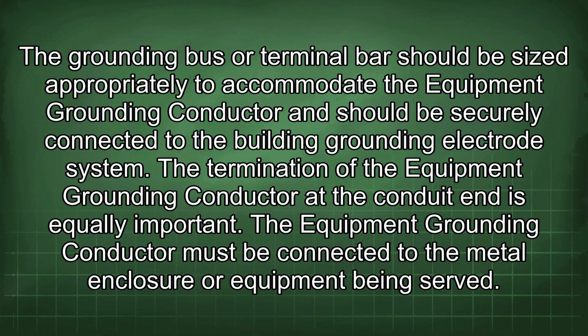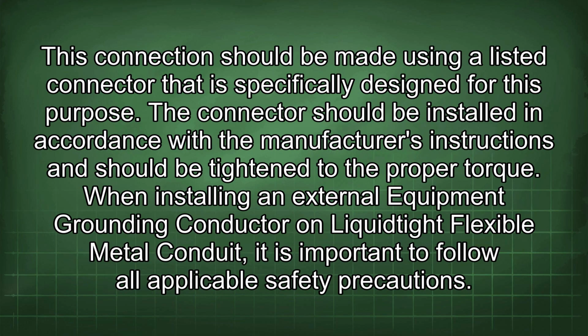The termination of the equipment grounding conductor at the conduit end is equally important. The equipment grounding conductor must be connected to the metal enclosure or equipment being served. This connection should be made using a listed connector that is specifically designed for this purpose. The connector should be installed in accordance with the manufacturer's instructions and should be tightened to the proper torque. When installing an external equipment grounding conductor on liquid-tight flexible metal conduit, it is important to follow all applicable safety precautions.